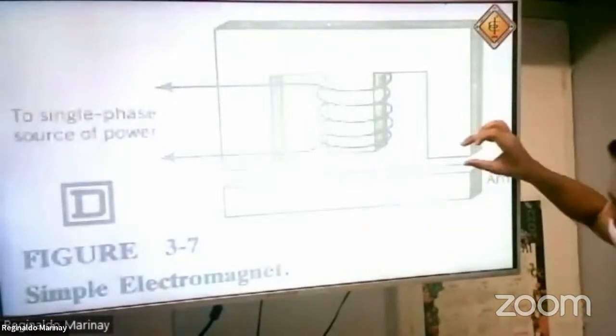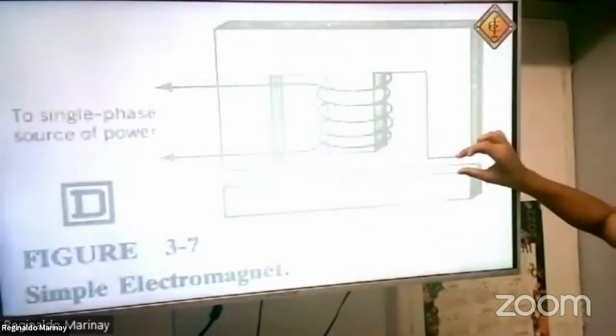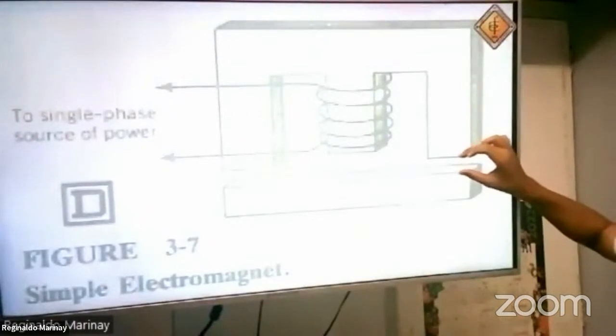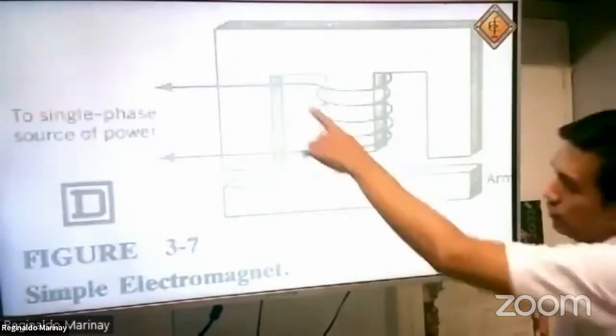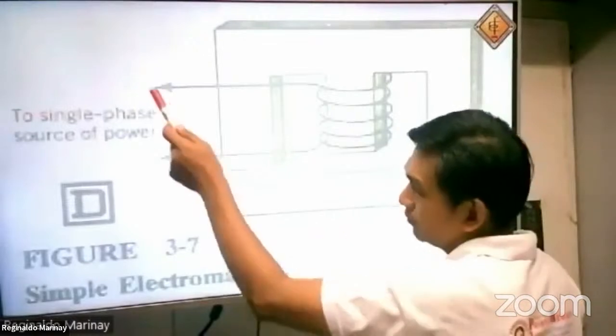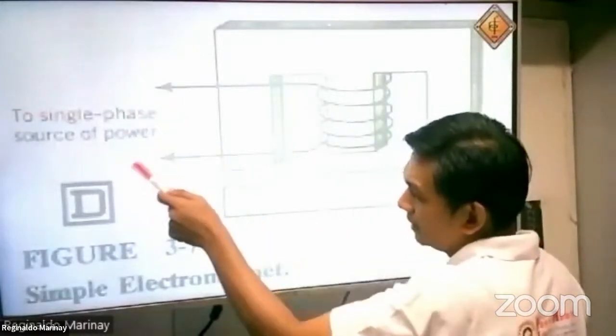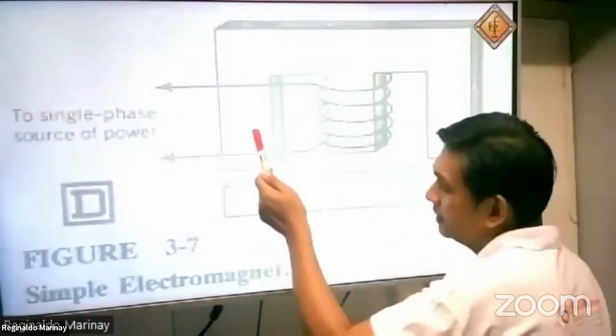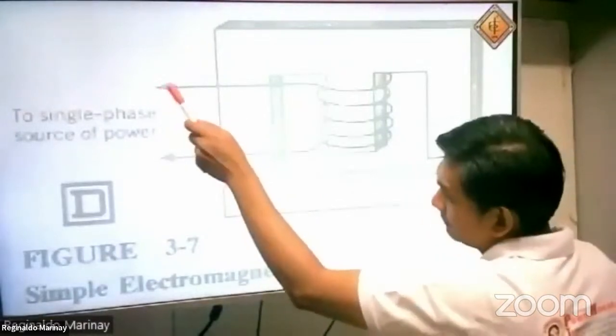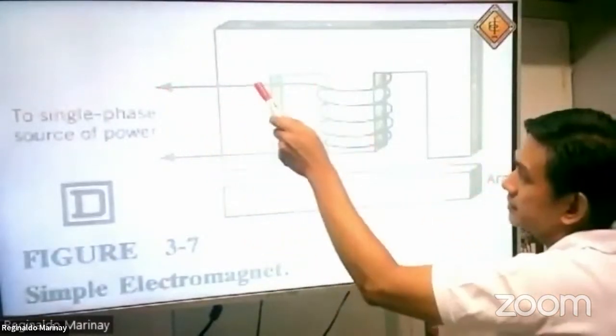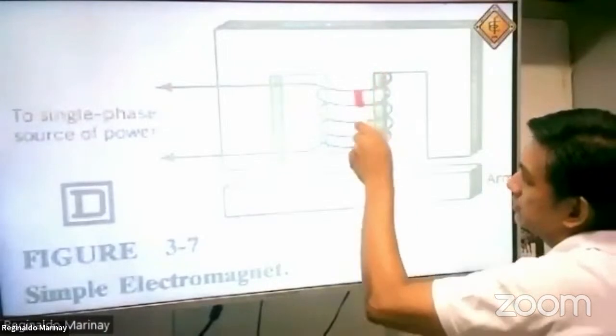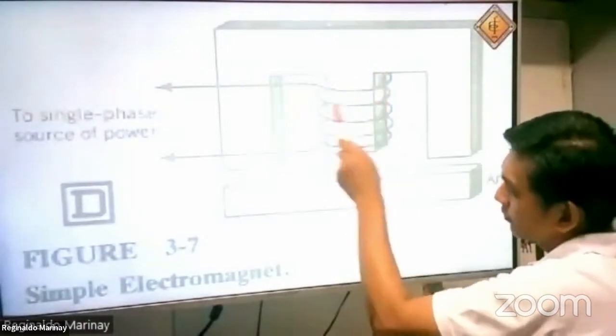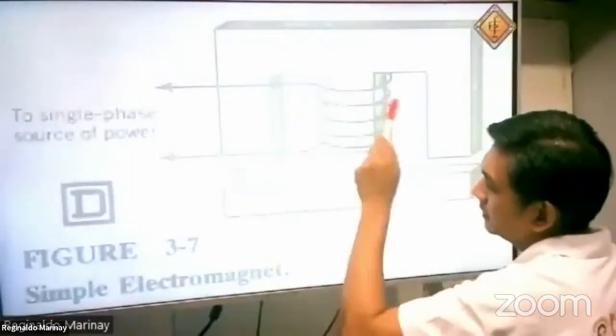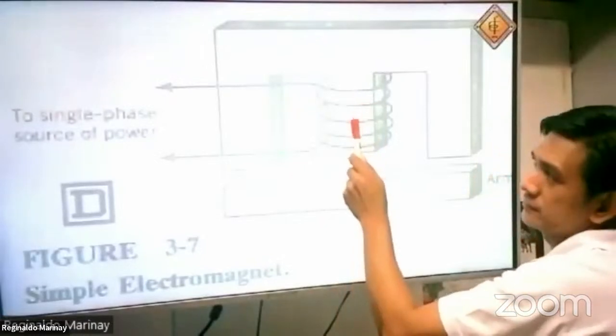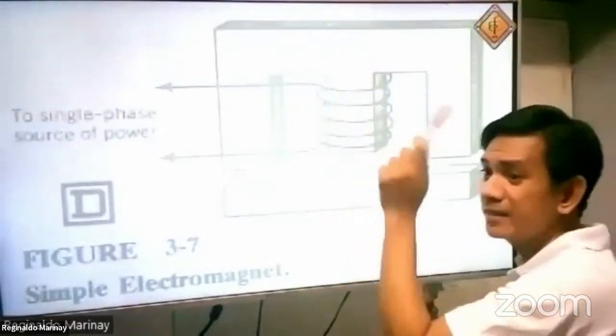This particular example, you will see this is open. Then as we energize this coil, we put this in line 1 and line 2 of the AC supply. The current would flow, let's say, from line 1. So it will flow to this coil. And then this core will become magnetized.